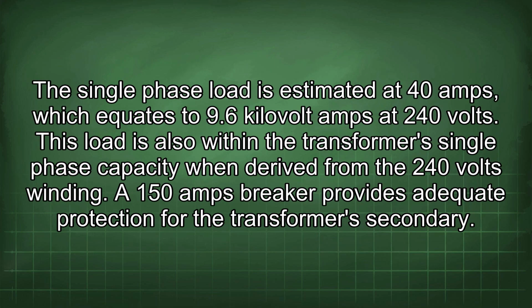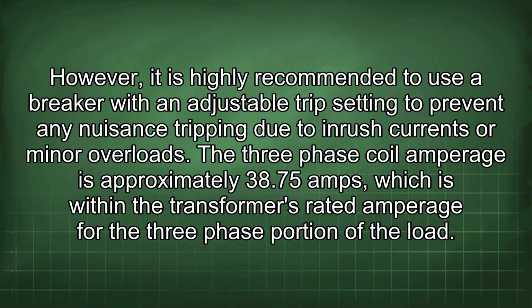The single-phase load is estimated at 40 amps, which equates to 9.6 kVA at 240 volts. This load is also within the transformer's single-phase capacity when derived from the 240 volts winding. A 150 amps breaker provides adequate protection for the transformer's secondary. However, it is highly recommended to use a breaker with an adjustable trip setting to prevent any nuisance tripping due to inrush currents or minor overloads.